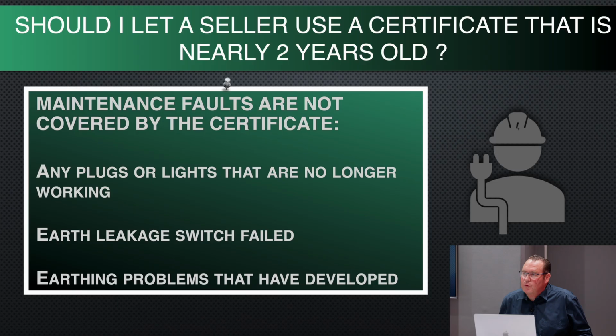I want to mention something about earthing problems quickly. We've seen this more and more recently - it's been happening for 10, 15 years, but it's growing. I think electricians that were in one company have moved to another and spread this idea that if you've got an old property... There are 2 types of earthing systems. In a new house you've got that white wire, twin and earth, or Surfex, with an earth wire in it. Or in a fairly new house, like a Parklands area property, you've got plastic conduit with live, neutral, and earth in it. But in an old house, like a Claremont example, you've got metal pipes with just live and neutral, and the metal pipe was your earth to that point.